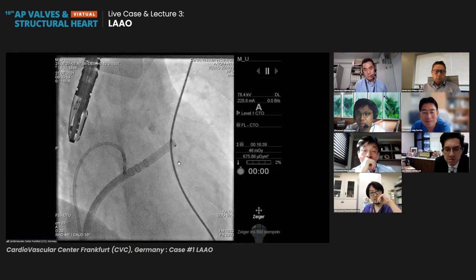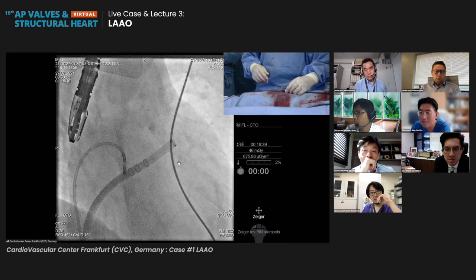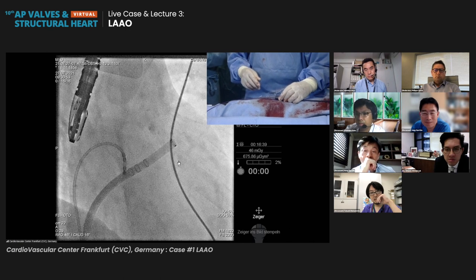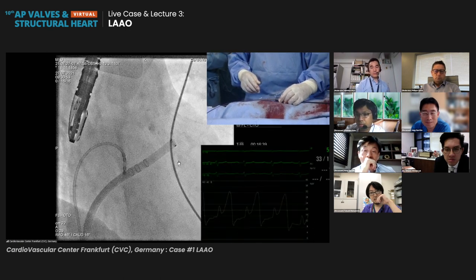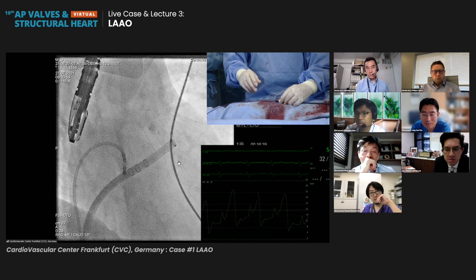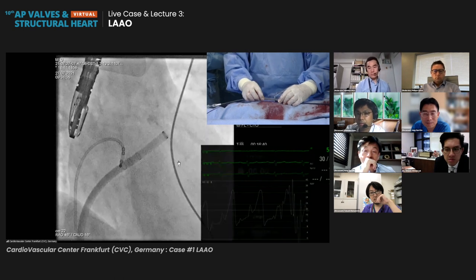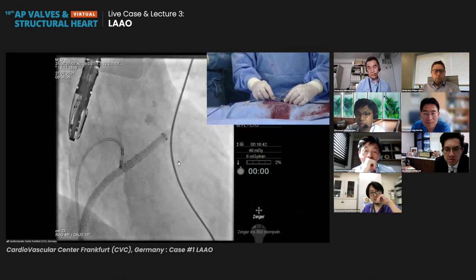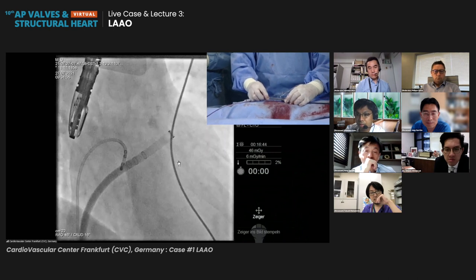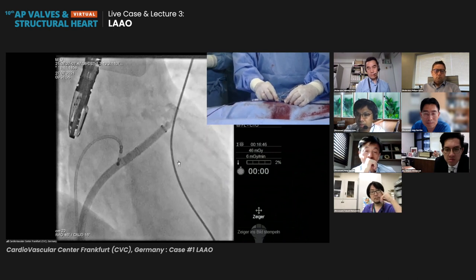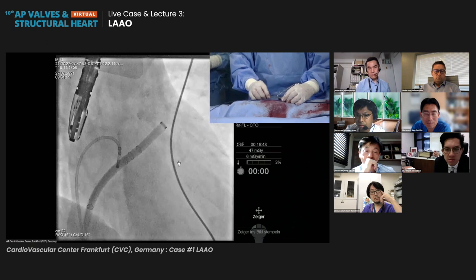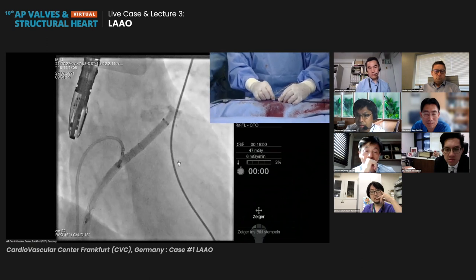Okay, we wanted to see the pressures actually. It's actually higher than before. It's now 18, so it's a good pressure. We want to have more than 10. The reason is that if the pressure is too low, then the appendage is kind of collapsed, which means you are measuring a smaller diameter than what the diameter really is.